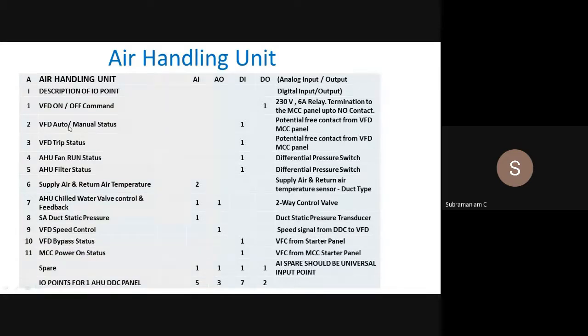So I have to take this auto position as a digital input from a potential free contact from the MCC panel. So the wiring has to be different. If we are buying the starter panel from somebody who normally supplies for a standard job without BMS, then when there is BMS on another project, the starter panel will have to have all these NO/NC contacts and additional relays, and the wiring has to be done for the BMS application. This is important that we should know and take care of. Then filter status will come as this.